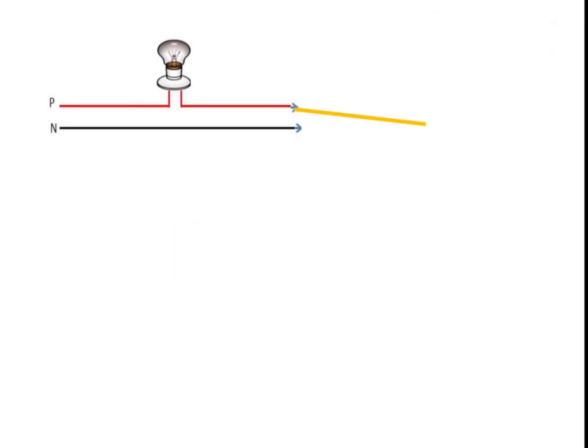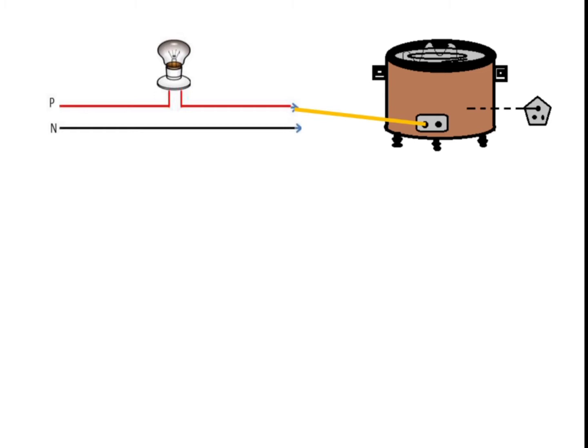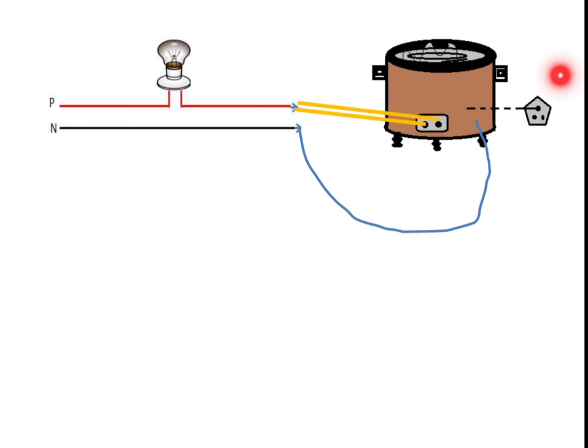Next, again we have the series lamp test, and under test we have taken a coil electric stove. We can do the connection like this, or either terminal can be taken here. There are two terminals; you can connect this one or the other way. Either one terminal, and the second probe, can be connected to the body, any part of the body, anywhere, since the body is always connected to the earthing terminal. So you can check with the cord also. It's best if you do this test with a cord, though you can do it either way.